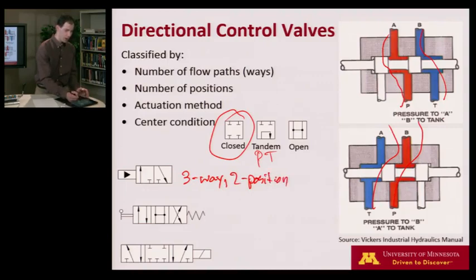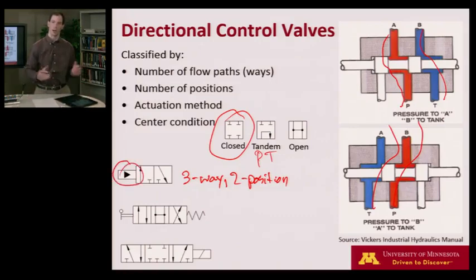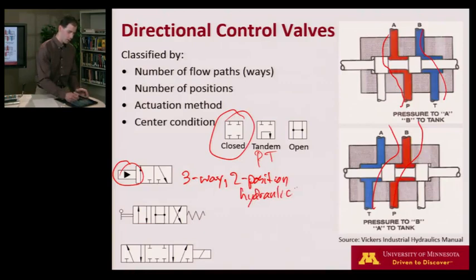Then I look for the actuation method. What's giving it away in this case is this symbol right over here. You'll notice that I have an arrow that's completely shaded in. That refers to a hydraulic pilot, so this would be hydraulic pilot operated. If that arrow was open, it would refer to a pneumatic pilot.